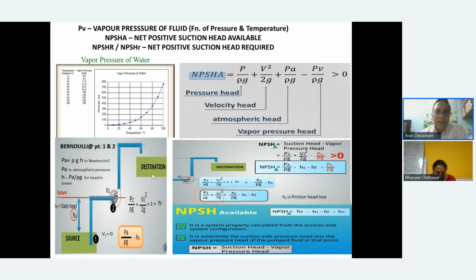NPSH available. NPSH-A is available from the given configuration. So this is nothing but, let's say if it is open to atmosphere, it is P by rho g. If it is a pressurized closed vessel, then you will have to put that pressure here. And P by rho g means everything is converted into head terms in meters. V square by 2g, where V is the velocity at this particular point. P is atmospheric pressure. And then you have PV, the vapor pressure of the liquid.